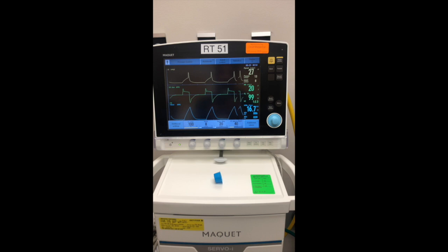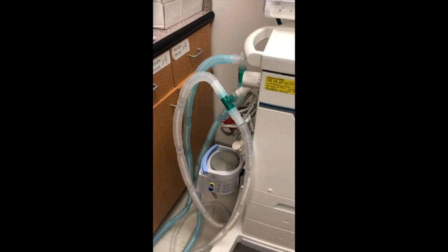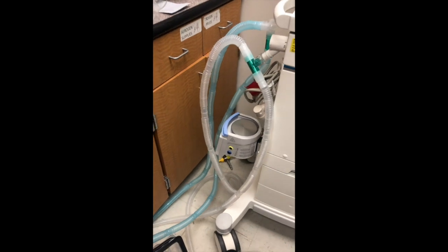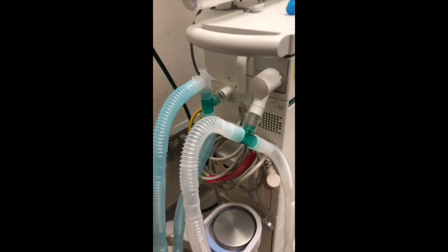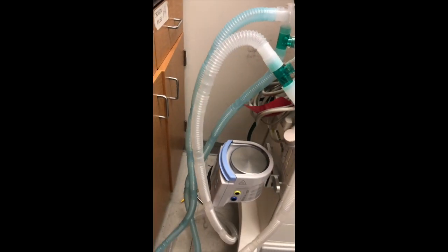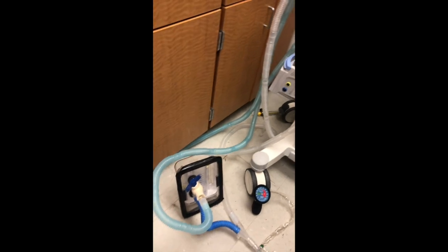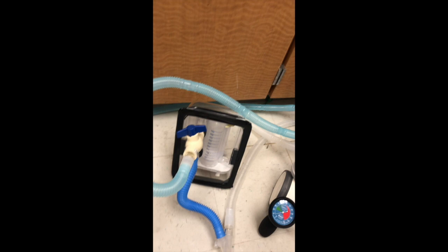So if you see the tubing, there is white tubing and there is blue tubing, and for convenience, blue tubing denotes the inspiratory limb and white tubing denotes the expiratory limb. If we follow that, the blue tubing is connected to the ventilator with a T-piece, and here I'm demonstrating how to ventilate 2 patients, which can of course be increased to 4 or 5 patients.